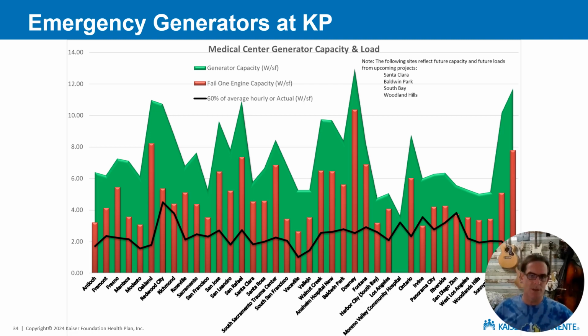We use 2 ways to try to determine that. First, if we have metering on the ATSs, then we use that number. Otherwise, it's based on 60% of the average hourly load from the historical electrical data to that facility. The variance on that number is quite a bit less. The average is about 3.5 watts a square foot. And that is an estimate of the load that we would have during an emergency, right? So as we're following code here, we are oversizing our generators. And I've been told for years that this is the code's fault. It is a known problem. Pretty much all of our electrical engineers know when you size generators according to the code, you are oversizing your generators.